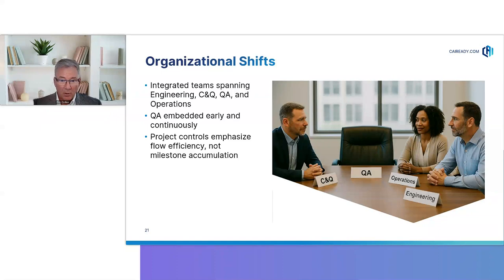When QA is not at the table early, as depicted in the slide, teams often proceed with assumptions about acceptable evidence only to face late-stage rework, rejustification, or rejection that drives delay and erodes confidence in the approach. Project controls need to evolve as well. Instead of tracking progress by document milestones, teams should focus on flow efficiency, how smoothly work moves from design to execution to approval. These shifts do not require major organizational restructuring. They require new collaboration patterns and shared accountability for outcomes. When organizations align around flow instead of handoff, iterative C&Q becomes sustainable rather than heroic.